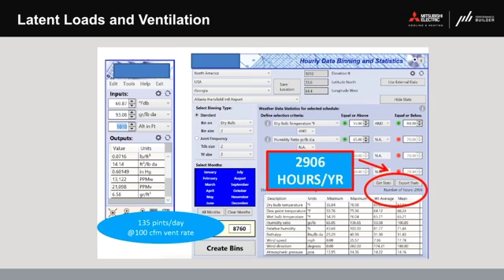And then we're also looking at the conditions where we have more humidity outside, humidity ratio. So that humidity ratio, you'll see, has units of grains per pound. And again, don't let your eyes cross here. It's just an amount of water. And so for reference here, our design conditions of 75 degrees indoor and 50% relative humidity equates to 65 grains per pound. So what I'm looking at here are humidity conditions that are above that 65 grains per pound, because again, we're considering ventilation loads. So that means if we're bringing outside air in and it has more moisture than what we want inside, then that's going to be an additional load that we have to consider.